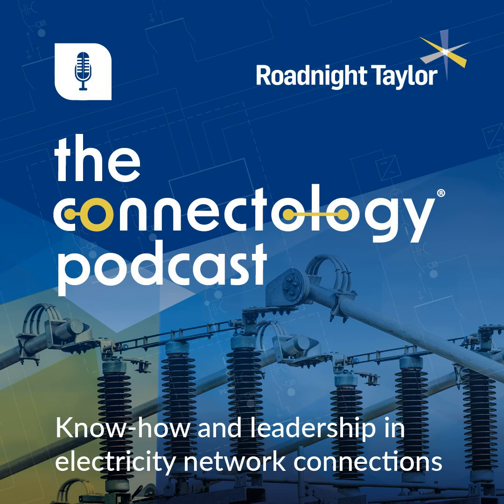But you have actually highlighted that there are some challenges associated with these connections. So what are the main issues with tertiary connections? The first one to highlight is really around constraints. A tertiary winding connection is obviously made, as I was describing a bit earlier, into a supergrid transformer. So anytime that supergrid transformer goes off supply, so that could be for regular maintenance every year, could be for a fault, something along those lines, that tertiary connection becomes unavailable.